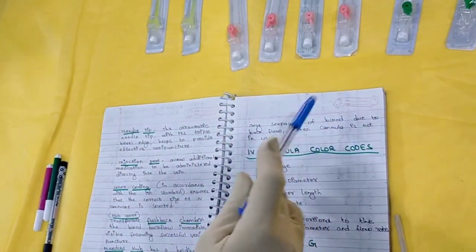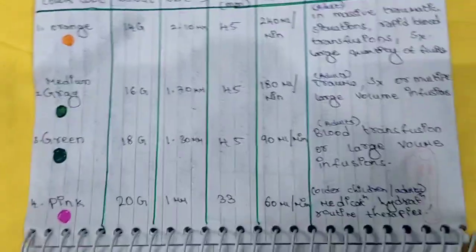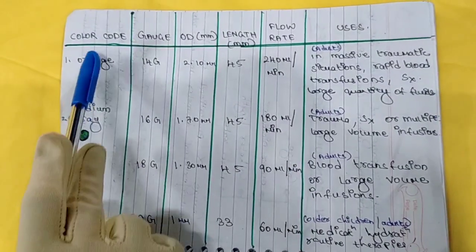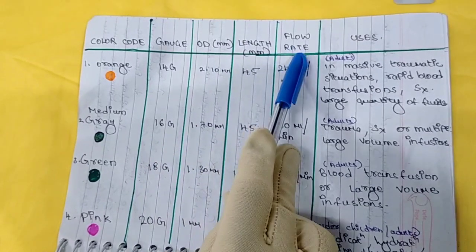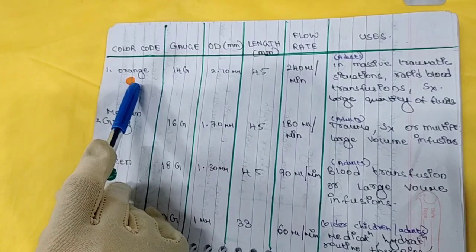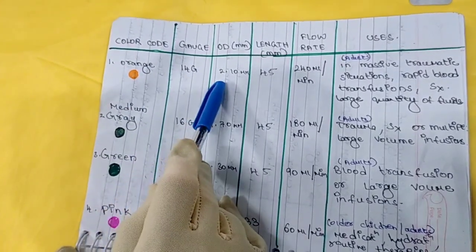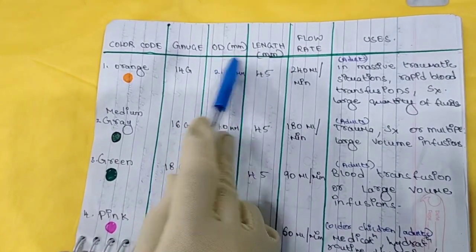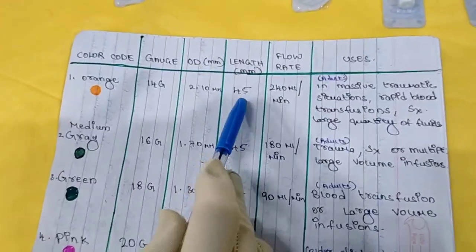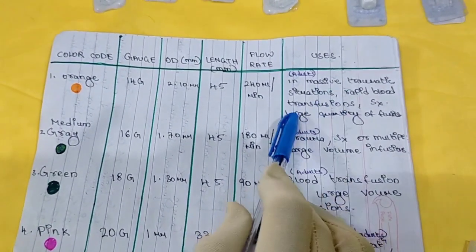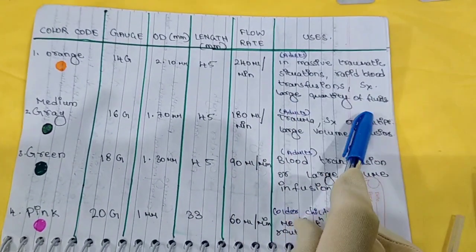I don't have all cannula sizes available, only pink, green, and yellow. But I will try my best to explain the color codes. The first color code is orange, which is 14 gauge. The outer diameter is 2.10 mm, the catheter length is 45 mm, and the flow rate is 240 ml per minute. This is used in traumatic situations requiring rapid blood transfusion, during surgeries, and when large quantities of fluids need to be infused.